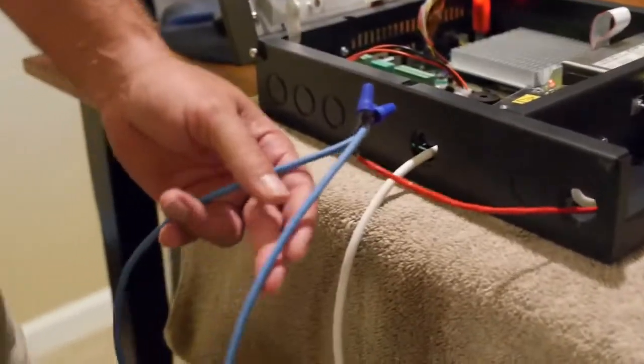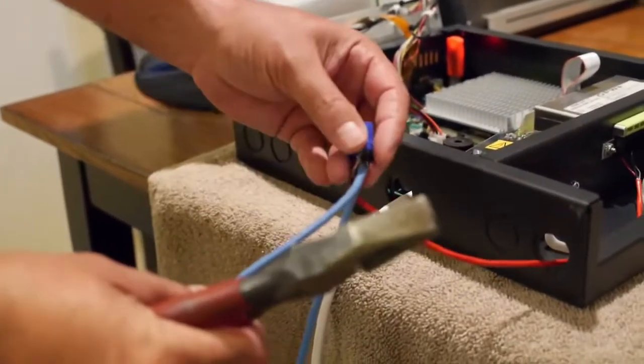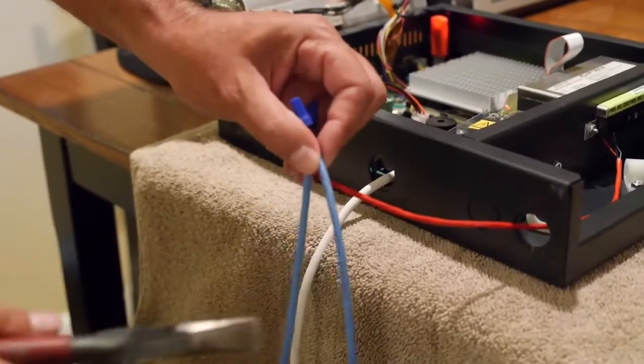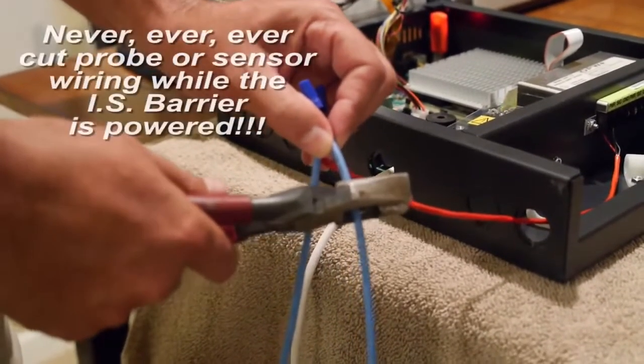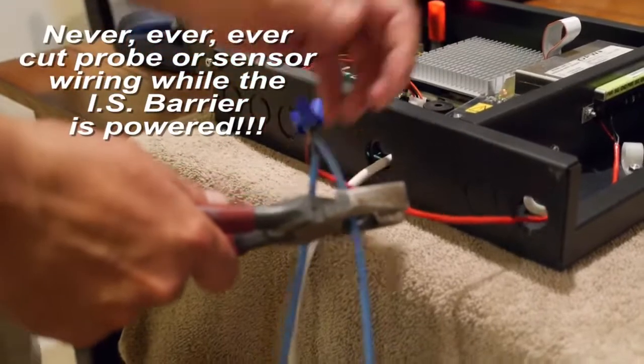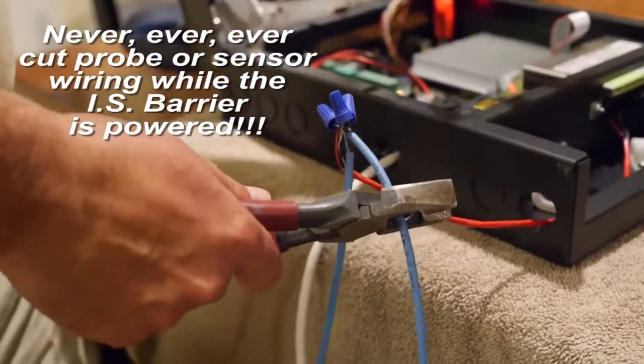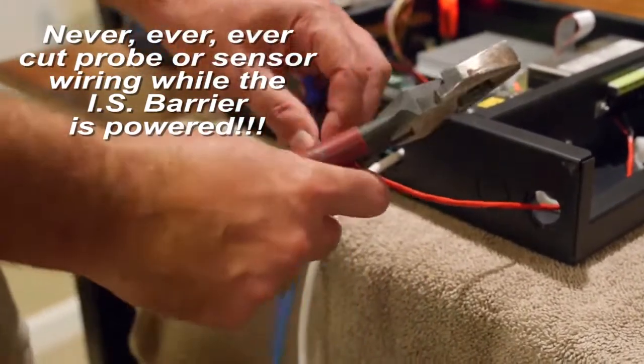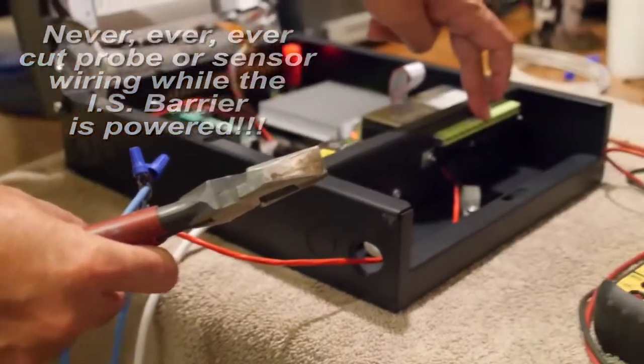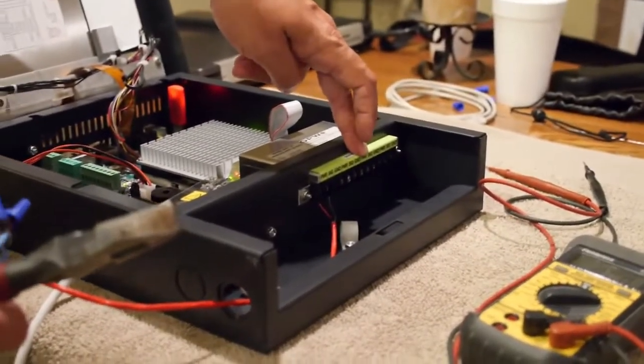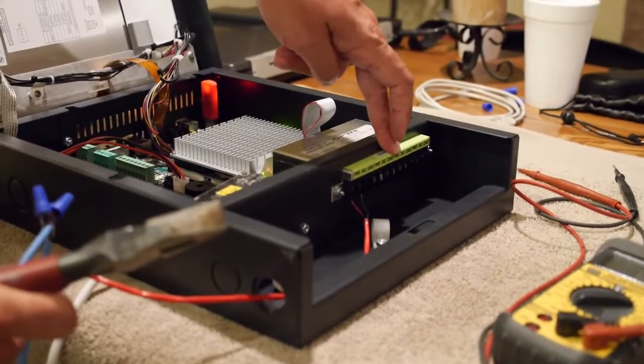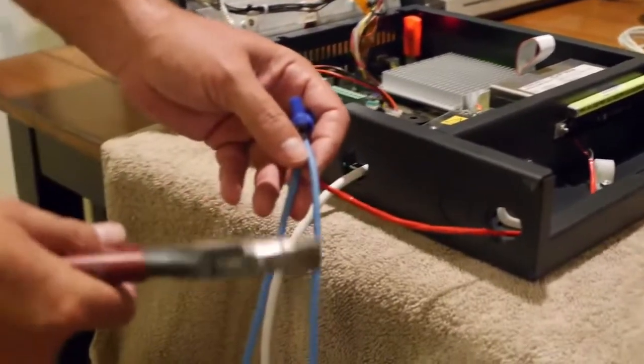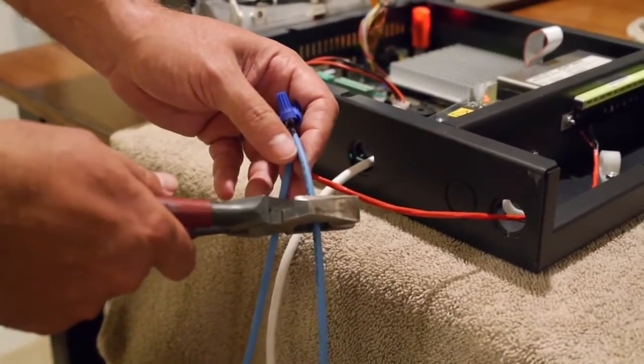What a lot of technicians will do in the field, if they want to remake this connection on a single probe, is cut across the probe wire, doing the exact same thing, and then they blow the barrier. So if you've done that, change it to an empty barrier position on the barrier, and have someone order another barrier for you. But please, if the console's hot, do not cut across.